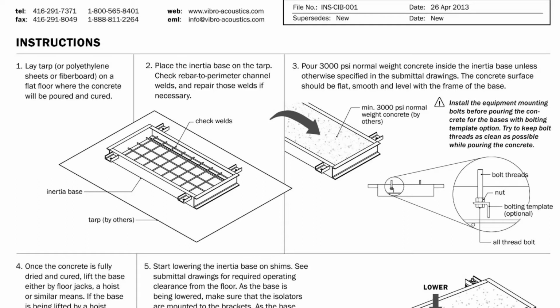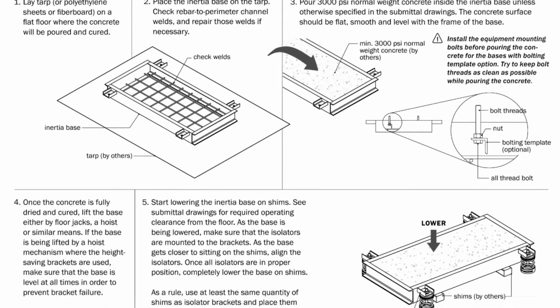For starters, note that the rebar is located in the bottom of the inertia base form and that the brackets are placed on the base with the toes of the channels pointed up. It is important that the inertia base be installed right side up to work properly. As should be obvious, the inertia base should be filled with concrete. This project didn't use what's referred to as a bolting template, which is used to pre-locate hold-down bolts for equipment, so we won't have to check for those.